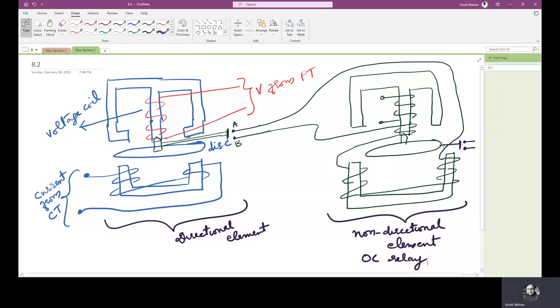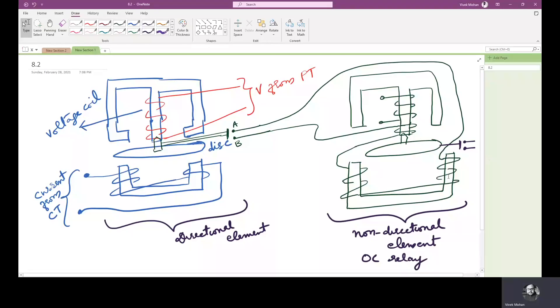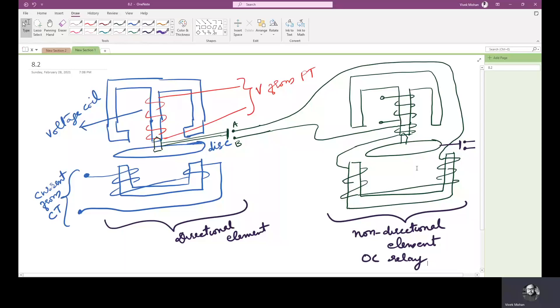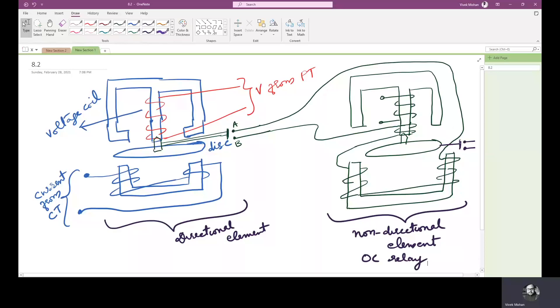The relay will not send a trip signal. Thus, the secondary winding of the lower magnet of the non-directional element remains open and hence the non-directional element is also inoperative. When the direction is not proper, this is inoperative, so the secondary winding is inactive. There is no interaction between the fluxes of primary and secondary winding in the non-directional element. Hence, torque is not produced and the disk will not rotate.